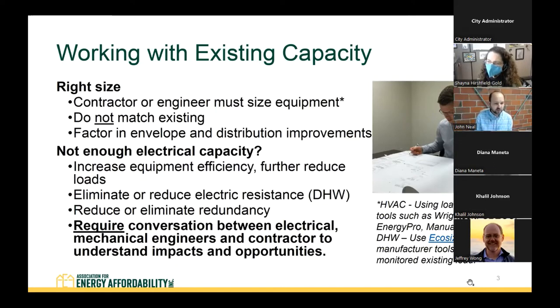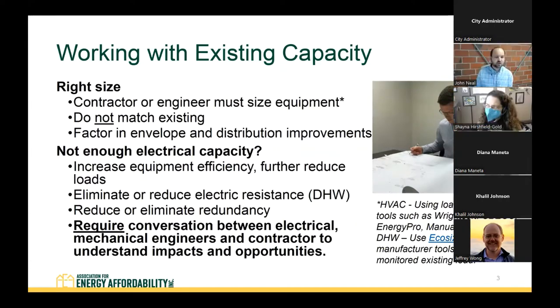Here are a few things we do: we look at increasing efficiency, reducing loads, and we're always looking to limit electric resistance in the system if it exists. Something came up on a project last week where the plumbing engineer had included full plumbing redundancy with the new water heating system, providing two heat pumps to supply water heating even though only one was necessary. While that's common and good practice for equipment breakdowns, it increased the electrical connected load and was problematic from a sizing perspective. So having that conversation with the whole team to understand all the impacts and opportunities of what's being designed and proposed is useful.